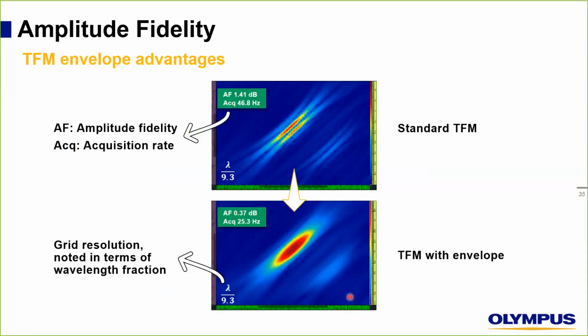To understand the next slide, I wanted to give some explanation. On the top, we will see a reading of amplitude fidelity and also the acquisition rate. When it's green, that means it's compliant with the code. When it's red, that means it's higher than 2 dB. The top picture will be the standard TFM. The bottom one will be the TFM with envelope. And we have the reading of grid resolution here noted in terms of wavelength fraction.